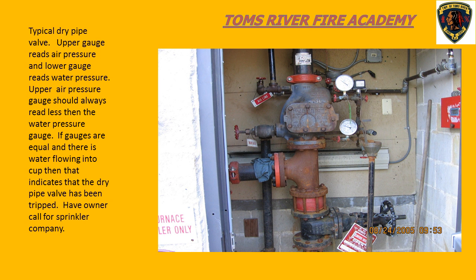This is a dry pipe system. Here is the check valve, the dry check valve. There's a clapper that sits in here. When the system activates, the clapper comes up, locks open, water enters the system. When we deal with a dry pipe system, a service provider needs to come out to restore the system. They'll take this plate off. They'll have to physically reset the clapper valve in place.